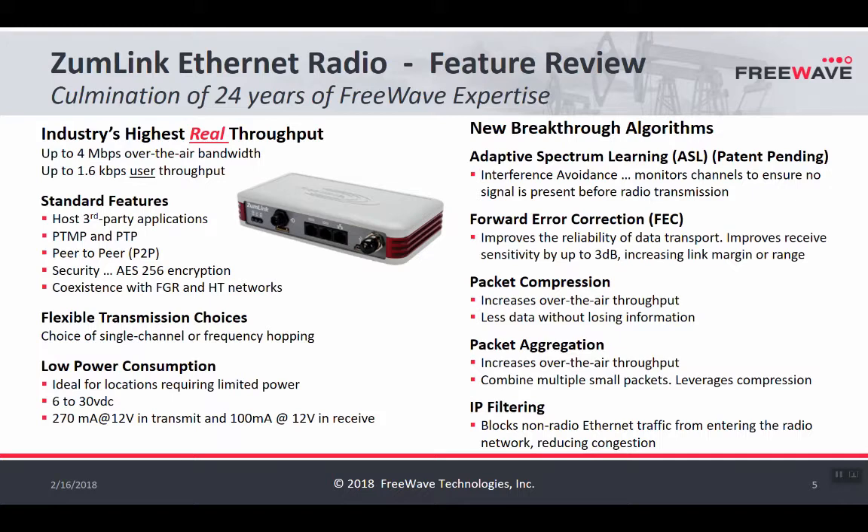ZumLink allows a lot more to be done with data than just sending and receiving over a radio link. It has point-to-multipoint and peer-to-peer capability, so any network topology can be achieved. Security is becoming a hot topic in the industrial sector, and all wireless communications are encrypted using 256-bit AES. For customers wanting to move from other FreeWave products to ZumLink, there is a coexistence plan for FGR and HT networks available for download from the website. ZumLink can also operate in a single channel mode or a frequency hopping mode, each with its own advantages.